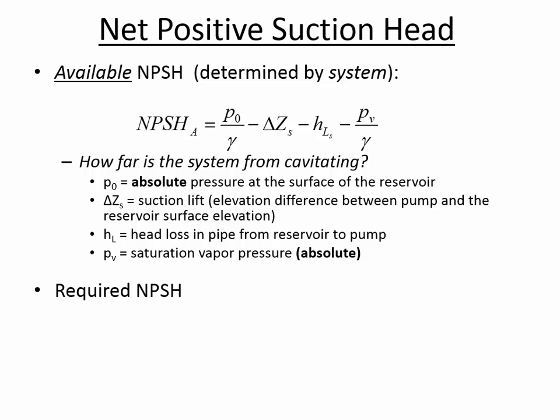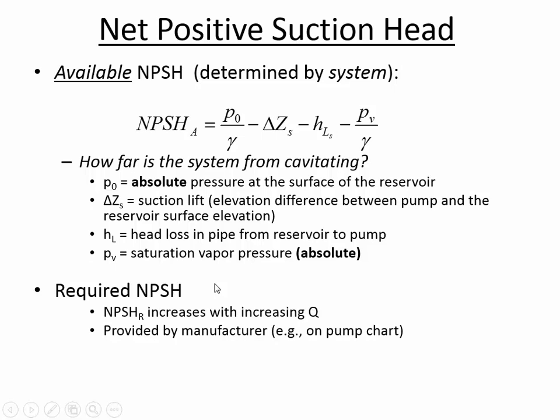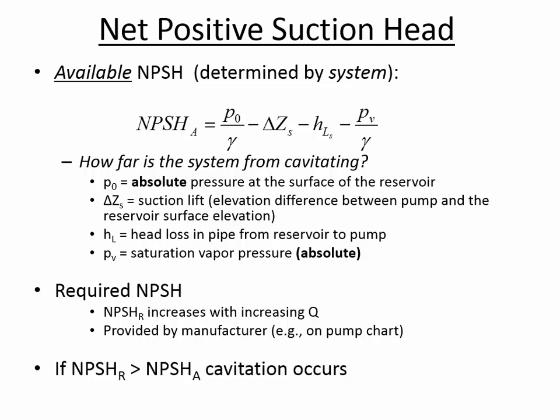And so you look at the system and you find out how much NPSH is available. And then each pump has a manufacturer specified required NPSH, and that's just based on the flow rate. And if we went back to that efficiency chart, you'd notice that it had the NPSH required on there for different flow rates. And anytime the required is greater than the available, cavitation occurs.